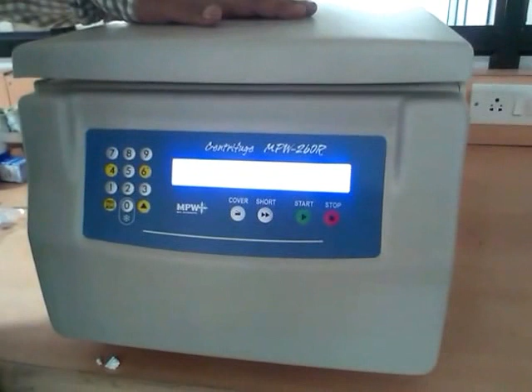The main features of this machine, the most important feature is that the compressor for the refrigeration is at the back of the machine, which requires very less space as compared to any other machine, where normally the compressor is on the side, which requires a lot of space on the bench. So this requires minimal space.